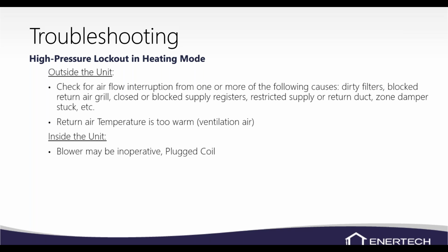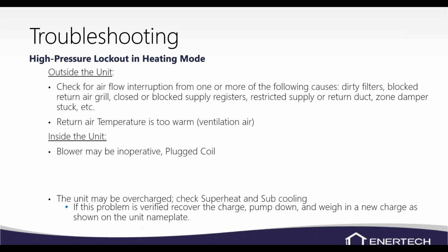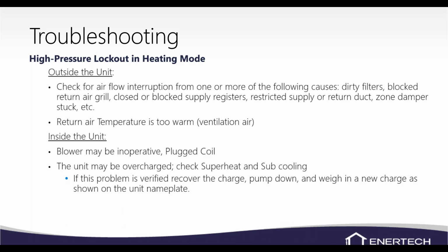So obviously check your blower, make sure the coil is clean. If they've run it during construction, that's probably going to be a bad thing. So make sure we're not running it during construction. So look at the coil, make sure it's not plugged, make sure your filter's not plugged up. If someone's done some work to the unit, it could be overcharged. So make sure we're checking our superheat and our subcooling.